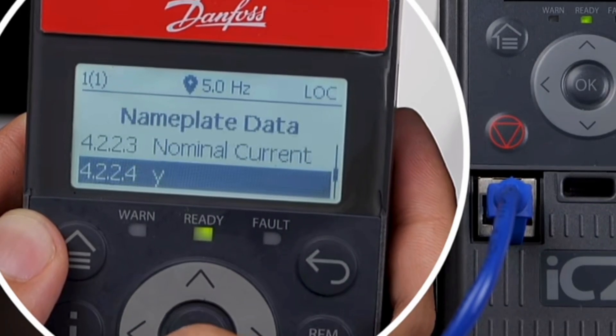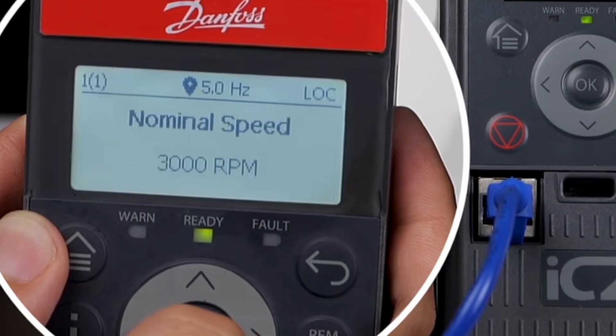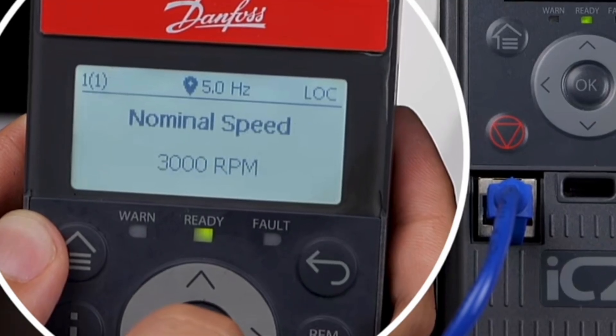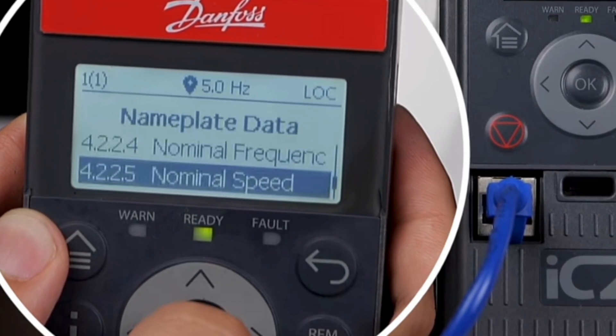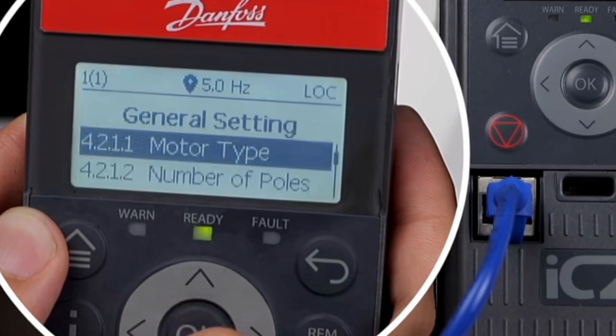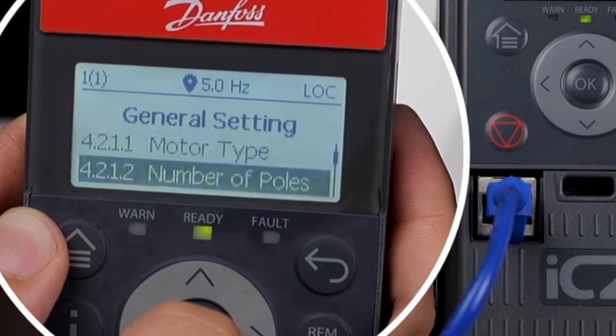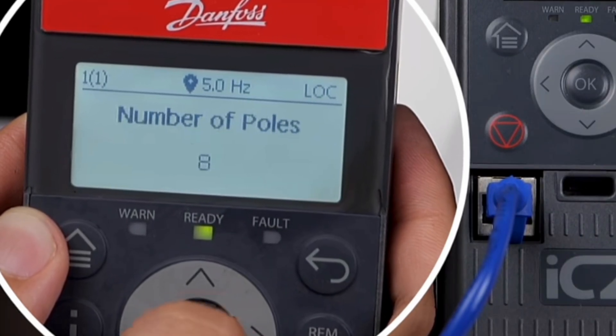Finally, select parameter 4225 and set the nominal speed to 3000 RPM. Then select parameter 4212 and set the number of motor poles to 8.